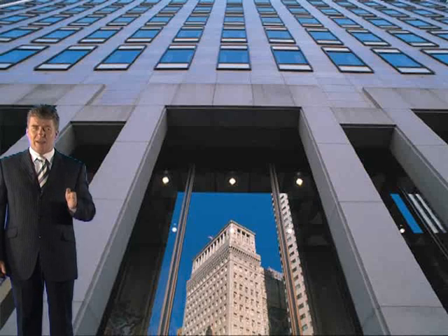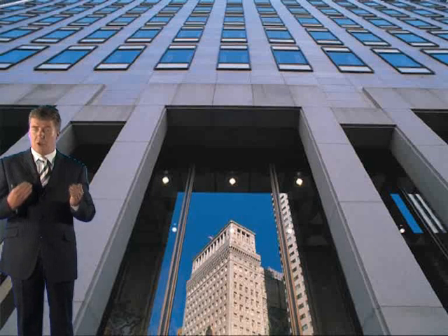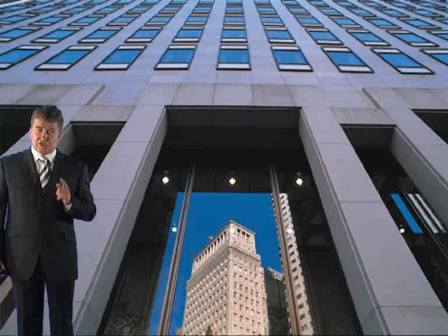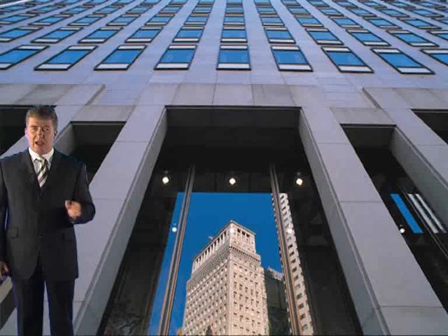Now, the effects of wind pressures on a ventilation system are not isolated to localised wind pressure effects alone. The wind pressures around the entire building envelope, the global pressures, will dictate the smoke flow patterns within the building and the effectiveness of the ventilation system design. There are a number of problems that you may encounter when considering the effects of wind. However, they can all be overcome. The ventilator may require modification, relocation, or you may have to replace natural ventilators with mechanical ones.